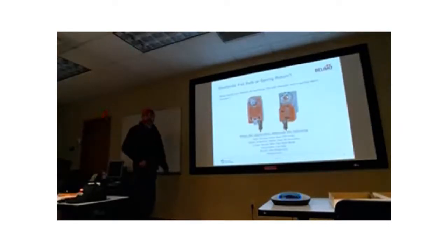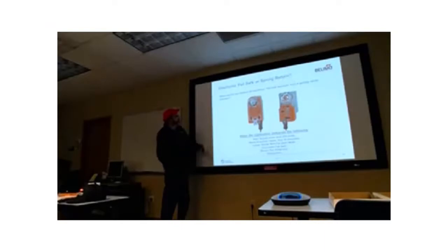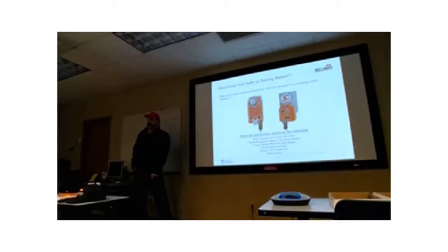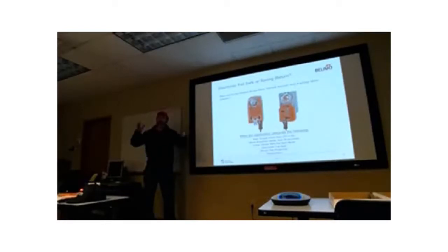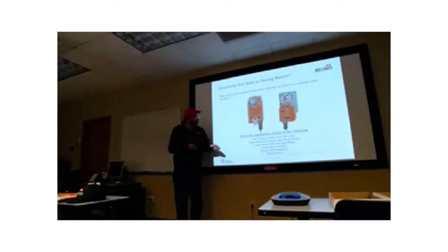So electronic fail safe - why would you choose electronic fail safe over spring return? I'll be honest with you guys, we very rarely use electronic failsafe here for damper actuators, for outside air, unless we get to dampers so big we can't deal with spring return. I'll show you our product line in a minute. But one of the things about electronic failsafe versus spring return is you can get more torque in a smaller package.